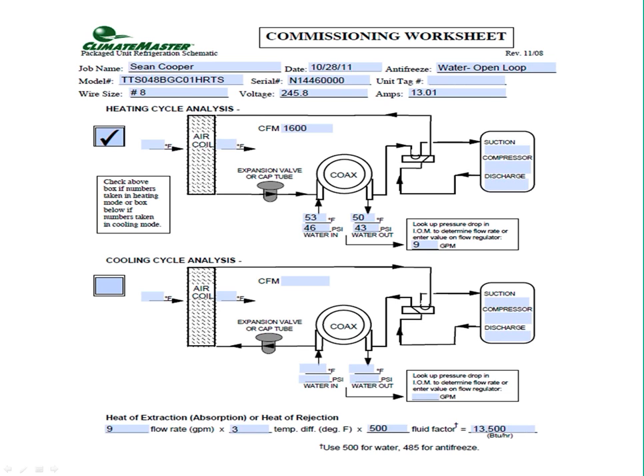My next step, based on the information that I see here, is that I would probably go get my 5 to 8 gallon bucket, my self-priming pump, and a couple of hoses, and I would isolate the well water system, and I would flush out that coax. What is likely going on here is you've coated the heat exchanger with some of the mineral deposits or whatever happens to be in that well water, and it's no longer transferring the BTU as it once did.